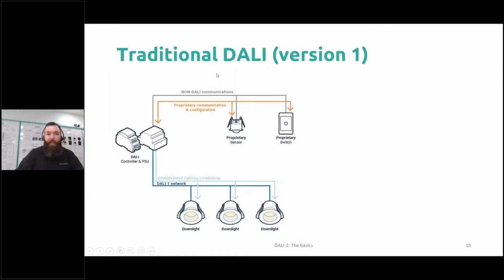We're looking first at a DALI 1 system with some separate network. This is fairly standard for a lot of systems because there wasn't any standardized way of putting in these sensors and switches. So what we tend to find is that there was some other communications protocol—this meant that out to every switch, every sensor, there was actually a separate network to the lights, to the emergency lighting, to the other relays in that building. Within that network, most of the time this was proprietary, and even within some of the big building management systems, the actual usage of these devices was specific to a manufacturer or a few manufacturers.